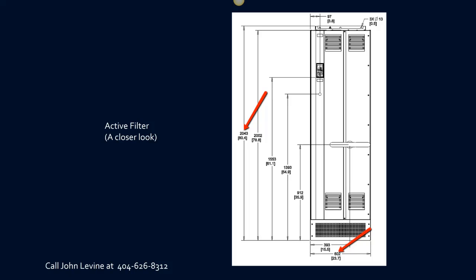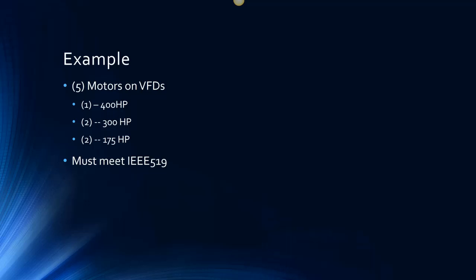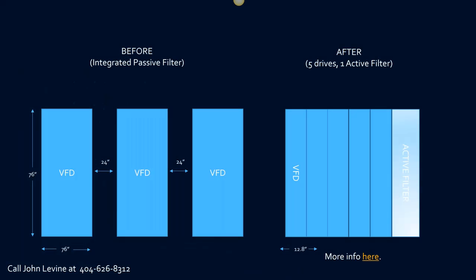So instead of having to have this huge enclosure with a passive filter and that requires all of these clearances, we have several individual drives on their own, all being corrected by one active filter. And so here's an example. Let's say we have 5 motors on VFDs. We have a 400, a 300, or 2 300s and 2 175s, and we have to meet IEEE 519. Before, what we have here is a VFD, and it requires 24 inches of space. And when we've gotten a little creative and taken a closer look at it, now we have 5 drives that are coupled together and one active filter, reducing the harmonic distortion of all 5 of those drives.